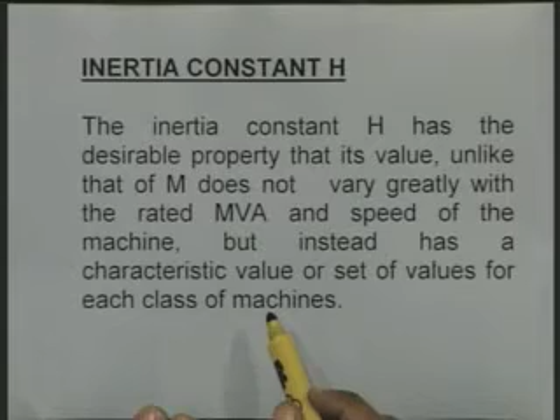I had very clearly, very emphatically told you last time that the coefficient M varies over a wide range depending upon the size of the machine, speed of the machine, type of the machine. However, the inertia constant H has some characteristic values, and in that respect H is similar to per unit reactance of machines. As you all know, the per unit reactance of synchronous machines have some characteristic values. Similarly, the inertia constant H also has certain characteristic values, and sometimes in the absence of specific knowledge about inertia constant H, we can assume some characteristic value and do our calculations. Manufacturers specify or provide the value of H on the MVA rating of the machine.